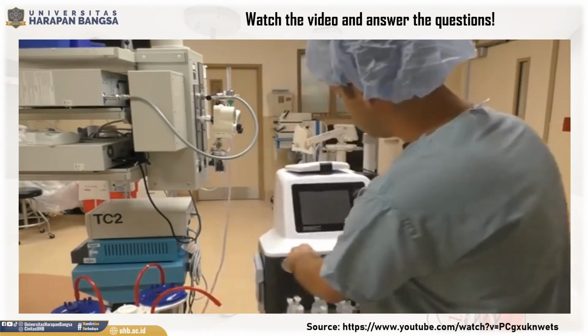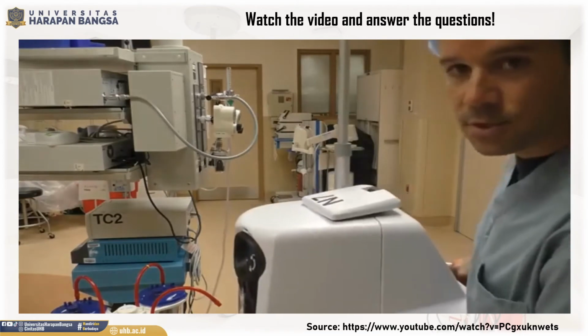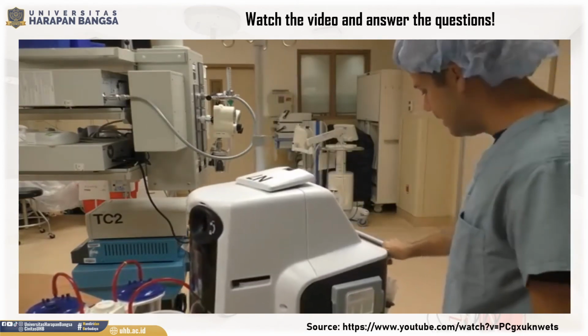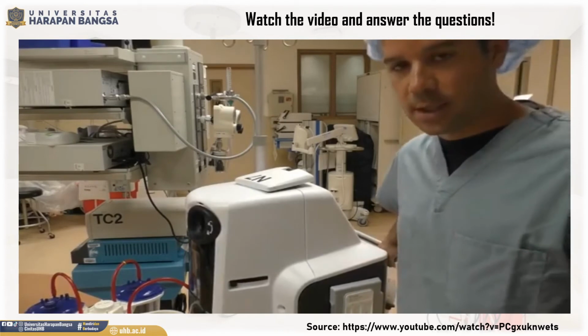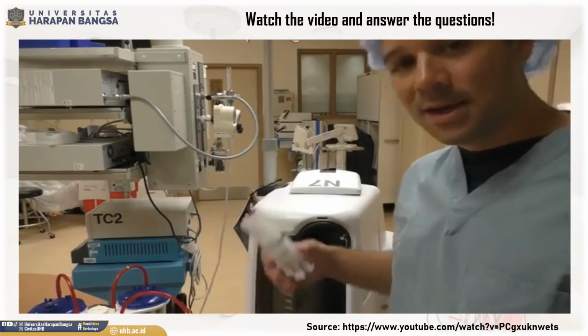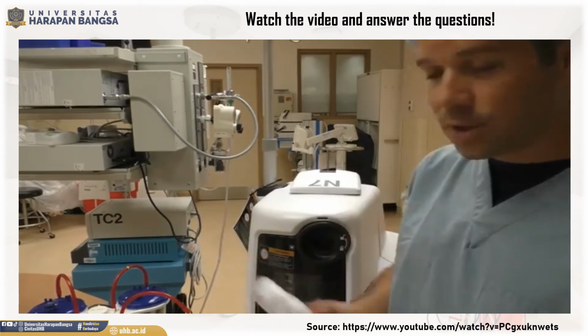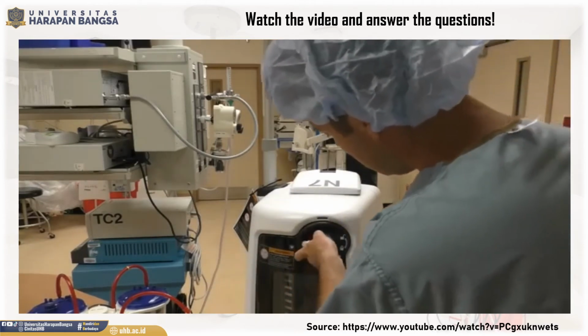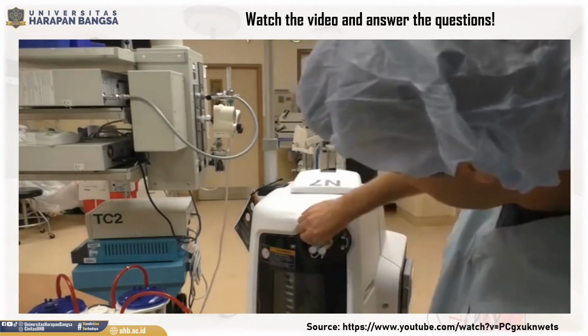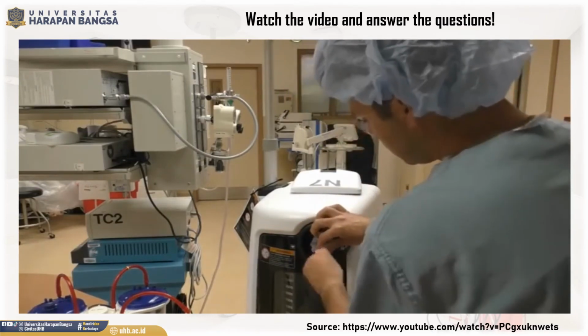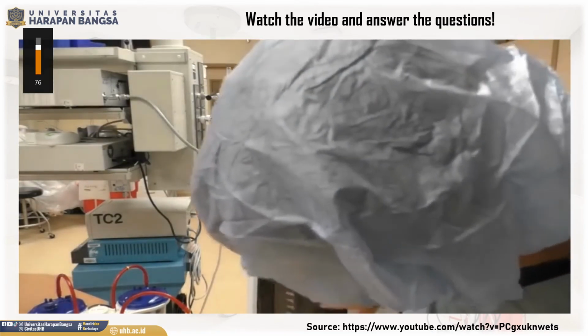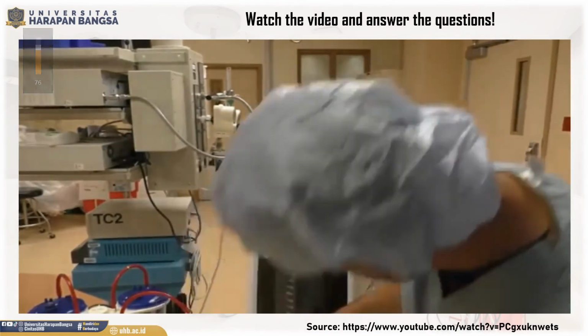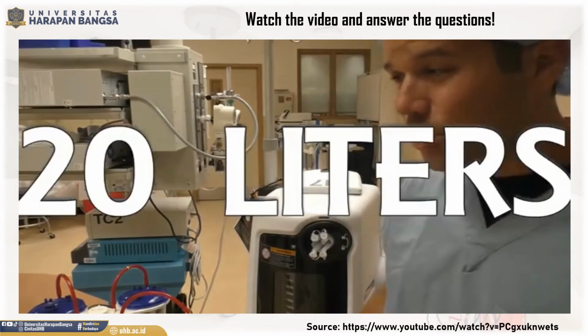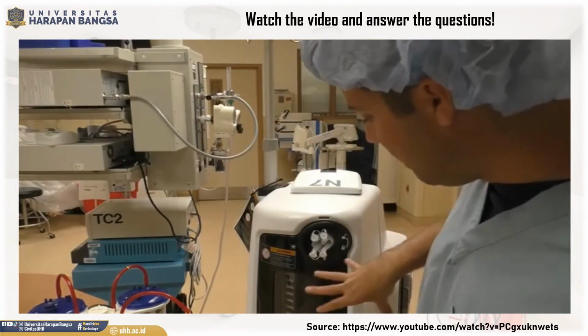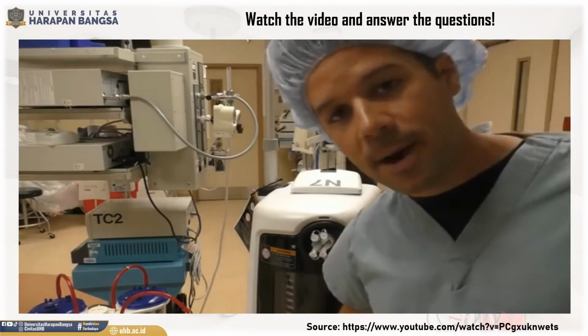So, we've got this guy. This is a Stryker Neptune. This guy is huge. It's a huge, giant suction machine. It's just got one little power cord, and we can just hook in one of these filters directly into it and lock it in place. It's got 4 little nozzles available to it, and this top part is really cool. It can hold up to 5 liters in this top part, and then this bottom part can hold like 20 liters. And you can even dump the top part into the bottom part.